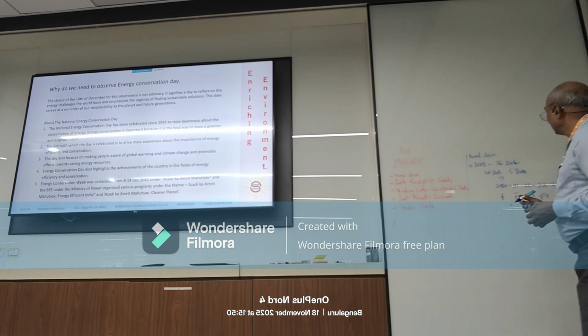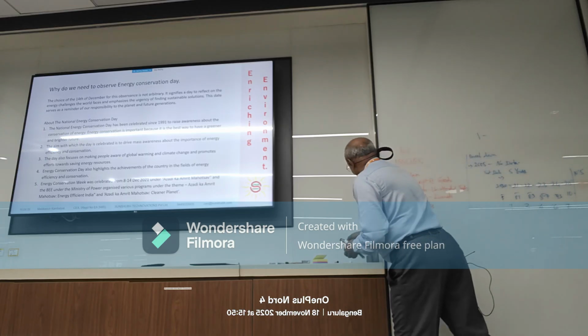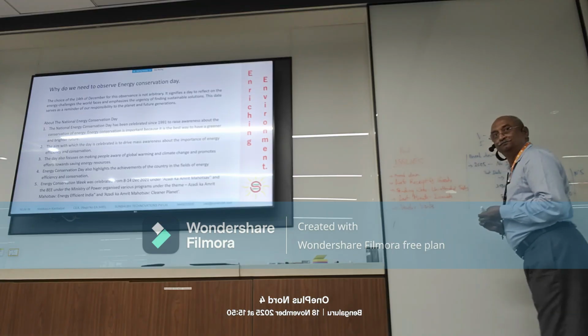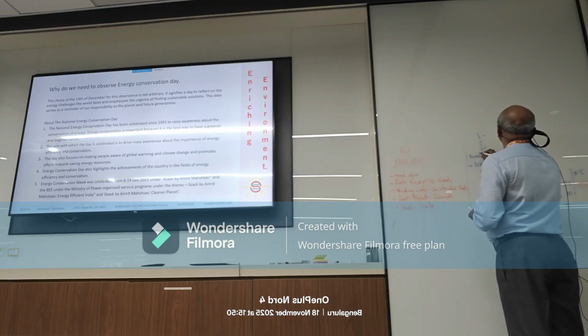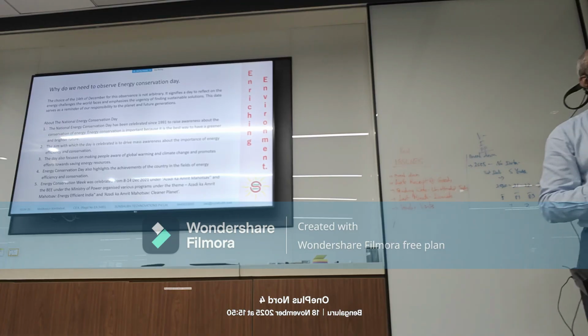Yes. But instantaneously, you can't wait for 1 day or 1 hour to assess whether the performance is correct or wrong. We will check the load amps using a clamp meter. Voltage, amperes, and power factor. Voltage and current. Power factor, okay? Cos theta. Power factor, right? But most often, what are you going to be looking at? Mainly current. Load current, amps.